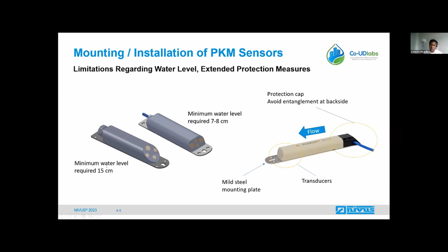And we already have two sensor versions. One is for water levels starting at around 7 to 8 centimeters. Below that, simply due to the blocking range and the property of the sound field, you cannot measure. And for the other sensor, the minimum water level that is required is around 15 centimeters.